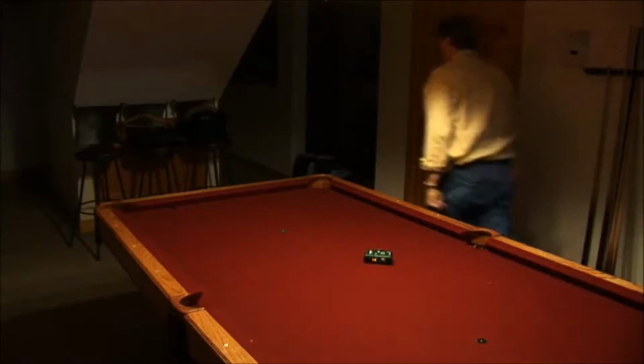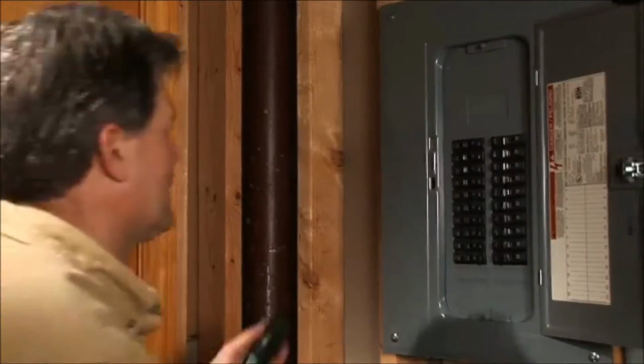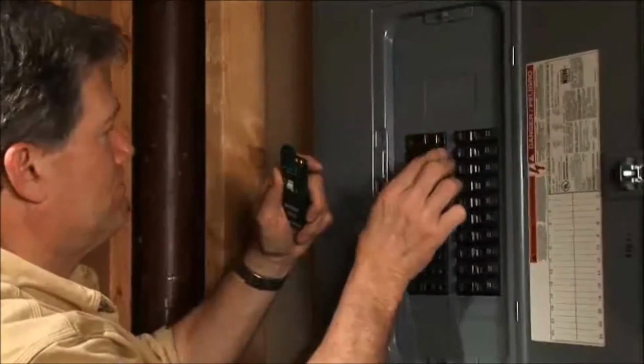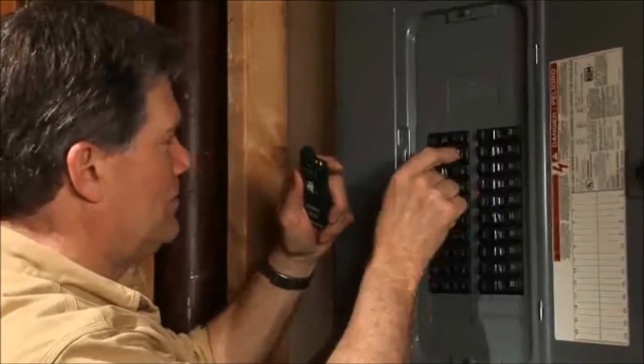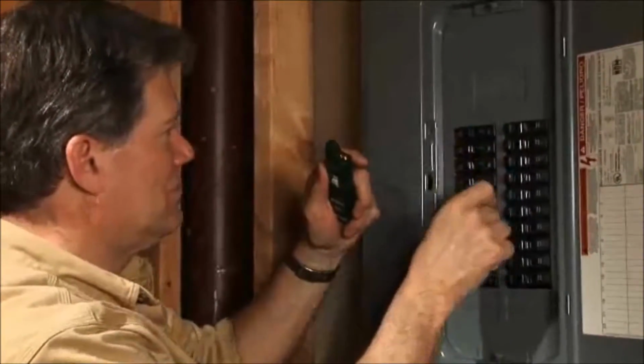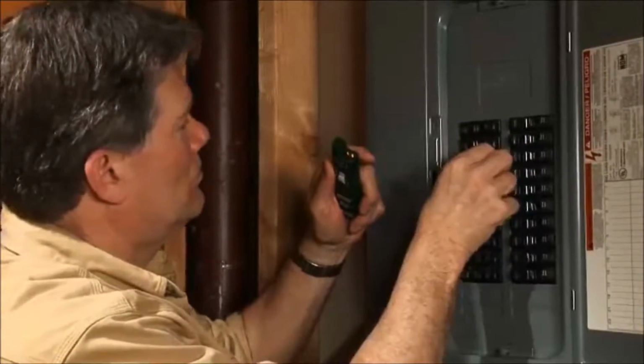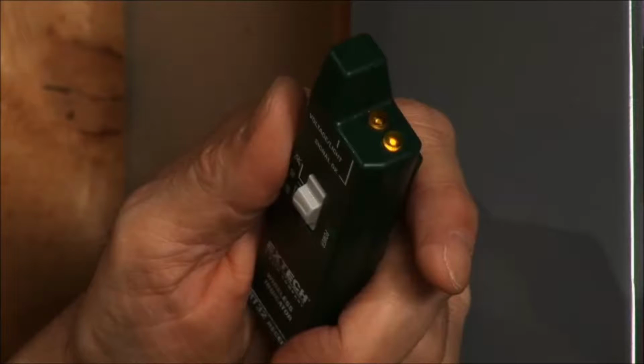Go down to the circuit breaker panel. Sequentially switch breakers on and off. Once power is interrupted to the light circuit, which is sensed by the transmitter, the correct circuit which powers the light is turned off. The tone alert and amber LED will go off, thereby identifying the light circuit.